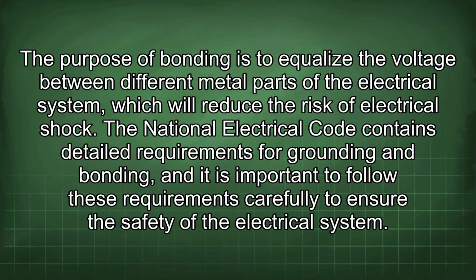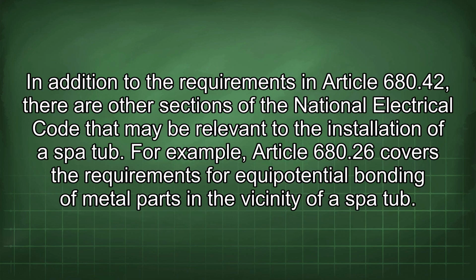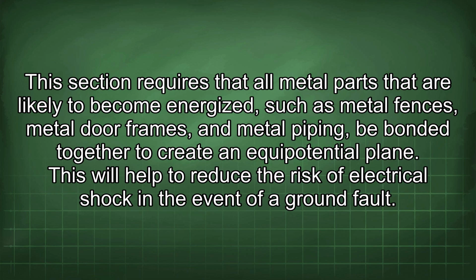The National Electrical Code contains detailed requirements for grounding and bonding, and it is important to follow these requirements carefully to ensure the safety of the electrical system. In addition to the requirements in Article 680.42, there are other sections of the National Electrical Code that may be relevant to the installation of a spa tub. For example, Article 680.26 covers the requirements for equipotential bonding of metal parts in the vicinity of a spa tub. This section requires that all metal parts that are likely to become energized, such as metal fences, metal door frames, and metal piping, be bonded together to create an equipotential plane. This will help to reduce the risk of electrical shock in the event of a ground fault.